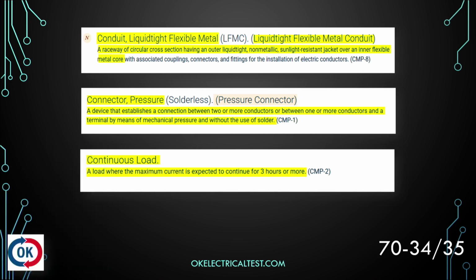And then we have continuous load. Continuous load, as defined by the code, is a load where the maximum current is expected to continue for 3 hours or more. So we may have to make an adjustment to calculations based off of the fact that something is continuous load versus non-continuous load. How do we define that? Is it going to run for 3 hours or more?